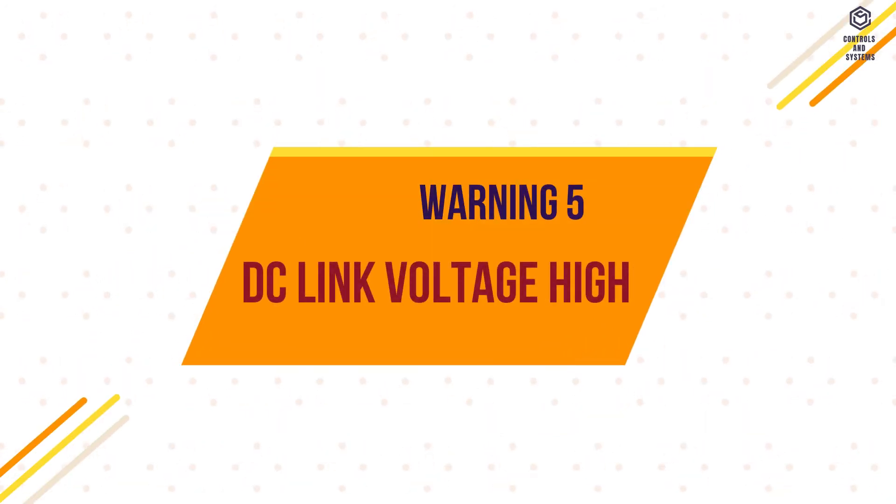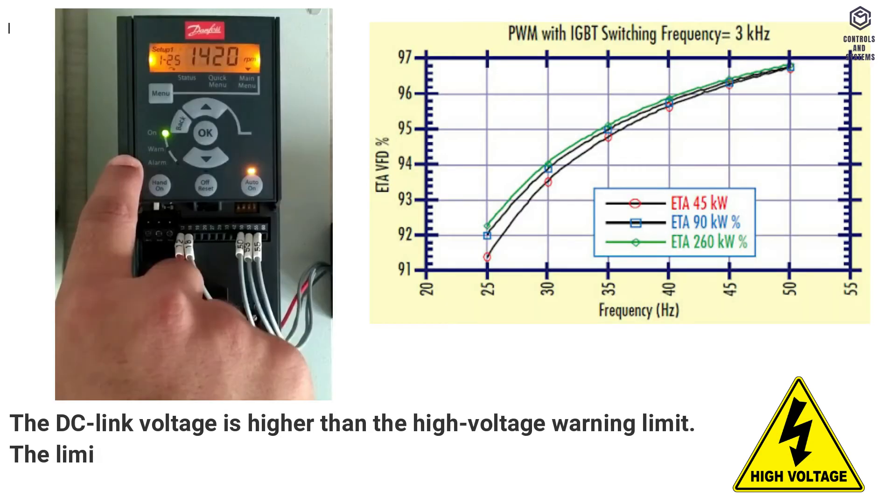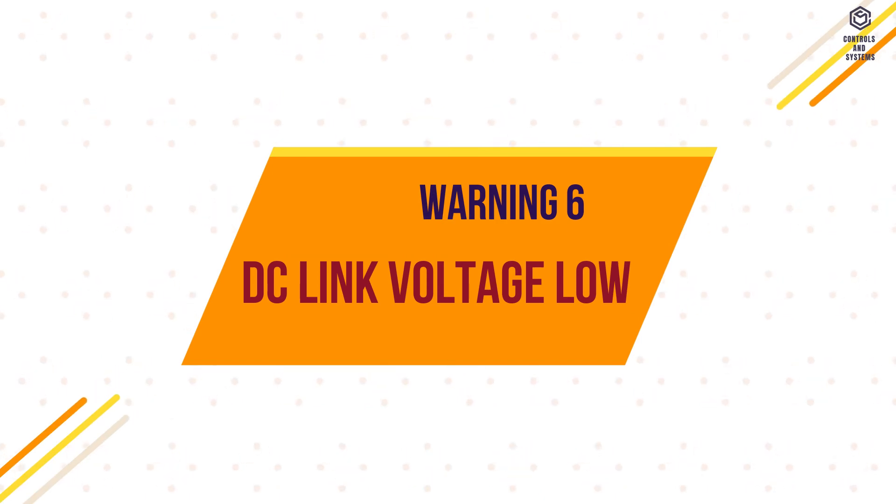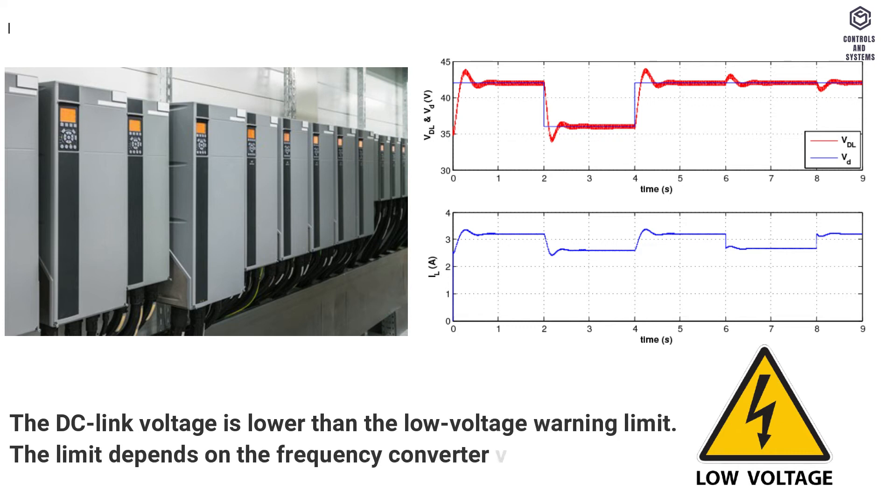Warning 5, DC Link Voltage High. The DC link voltage is higher than the high voltage warning limit. The limit depends on the frequency converter voltage rating. The unit is still active. Warning 6, DC Link Voltage Low. The DC link voltage is lower than the low voltage warning limit. The limit depends on the frequency converter voltage rating. The unit is still active.